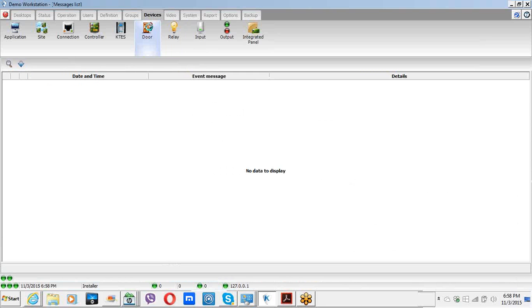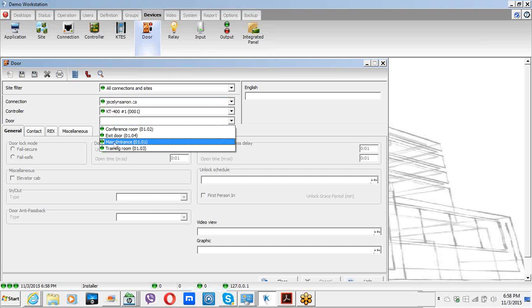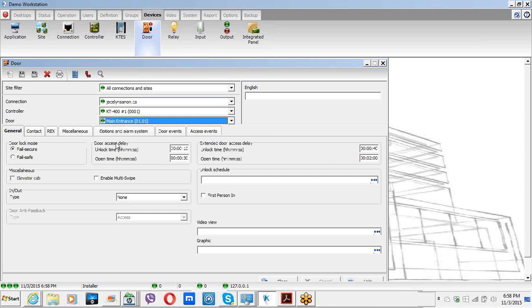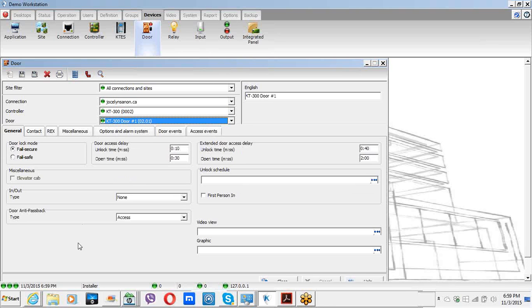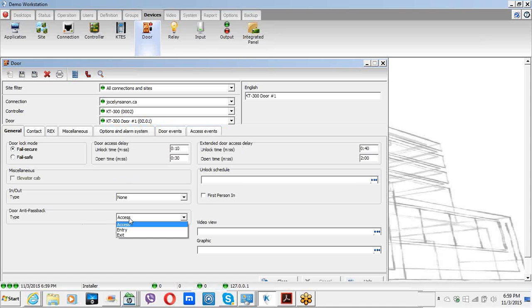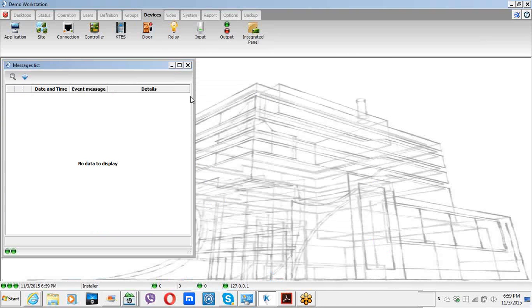For example, if I go Devices > Door and select my door — let's take Main Entrance on the KT400 — here you see the door anti-passback option. You can't set it up at the door level yet, because first we need to enable the anti-passback at the controller. It's the same for the KT300 as well; it will only work at the access level for now because it's not enabled at the controller level.